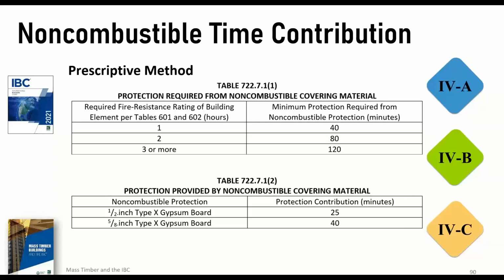So we know from our components that a sheet of 5/8 type X gypsum is good for 40 minutes. So we have configurations of 1, 2, or 3 layers. If we're going to use 1/2-inch gypsum, we have slightly less at 25 minutes. And if we're using 5/8 gypsum, we're back up to 40 minutes per layer.